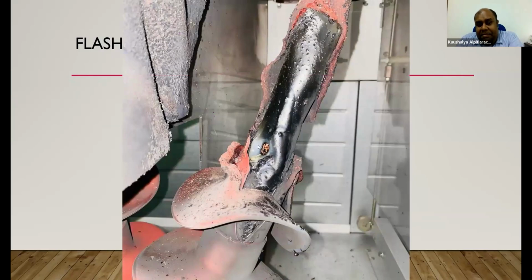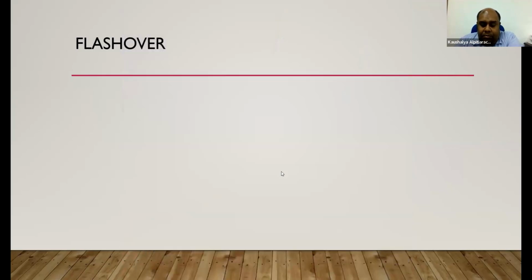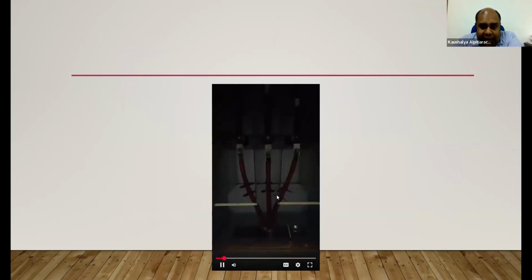This is the place where the fault originated. Most probably that tiny black spot can be the reason. The leftover of the semiconductor on the insulation might have, or a water bubble which is being left by improper workmanship. Yes, listen carefully.